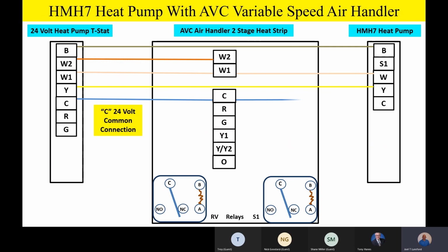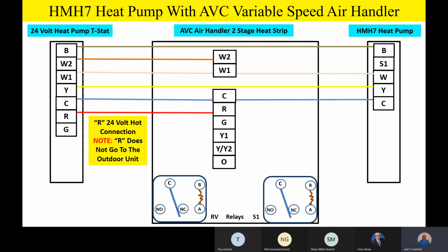C is our 24-volt common, and that goes all the way through from our thermostat to the indoor product to the outdoor unit. R is 24-volt hot, and even though this is a variable speed product, team, remember, we do not take R outside on the HMH7. That's just a thing to remember. We don't take R outside. It doesn't need the R terminal outside. G is our fan call, 24-volt fan call from the thermostat to the indoor unit, calling for fan.